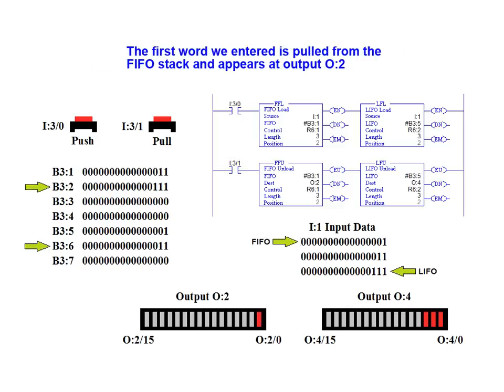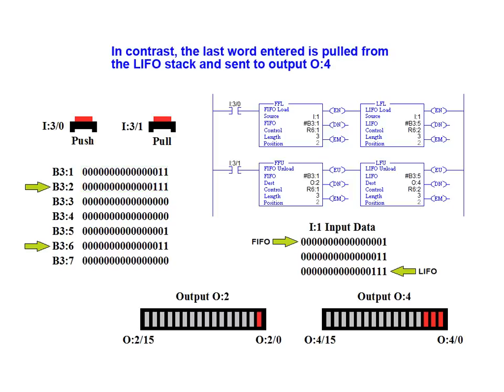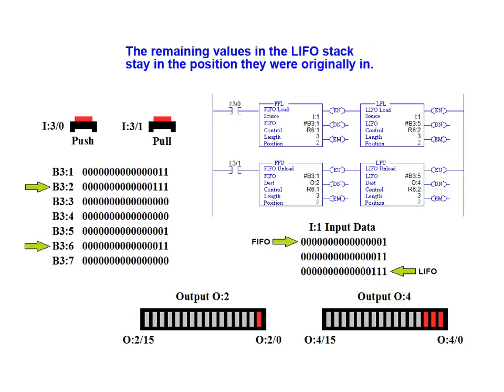The first word we entered is pulled from the FIFO stack and appears at output O:2. The remaining values stored in the FIFO stack have moved up one address location. In contrast, the last word entered is pulled from the LIFO stack and sent to output O:4. The remaining values in the LIFO stack stay in the position they were originally in.